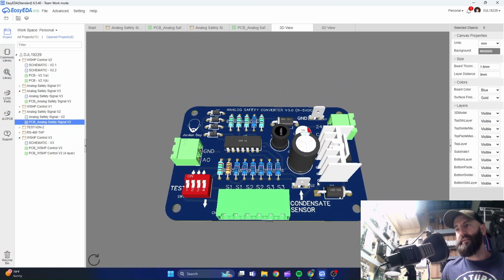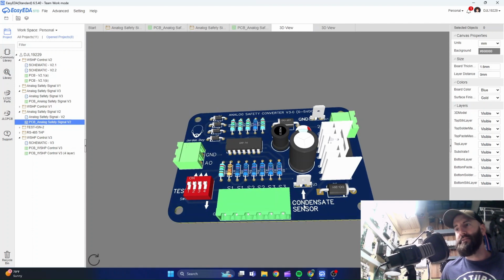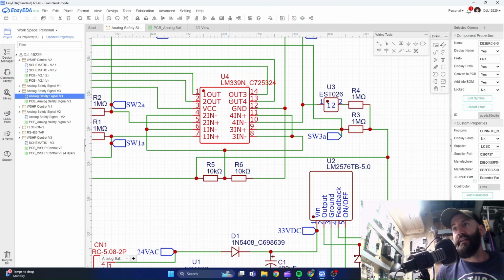So let me show you on the schematic how this condensate sensor works and how it's used just in place of that 4th safety. Back at the LM339, we're going to be using input-output number 4. And what we're doing differently with this condensate on this model is I'm taking my 2.5 volts that's coming after my voltage divider here, and instead of feeding into the negative like I did on the other inputs, I'm feeding this one into the positive. Okay. Now remember, output 4 is going to remain in a low state, which would be a no-fault state.